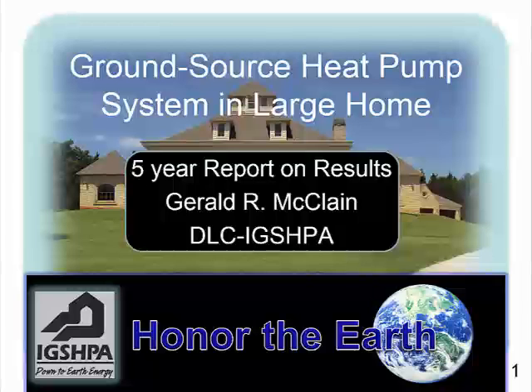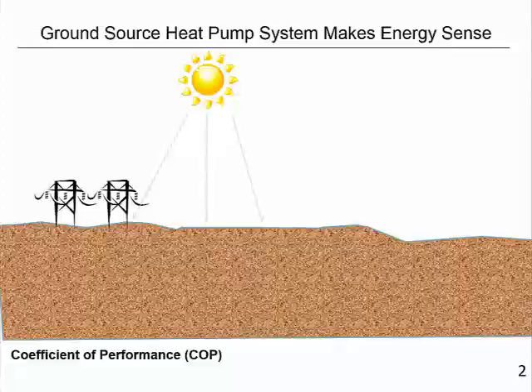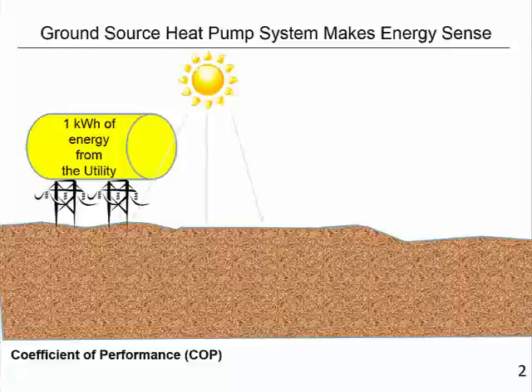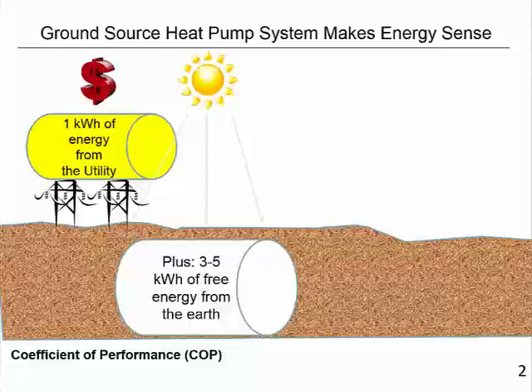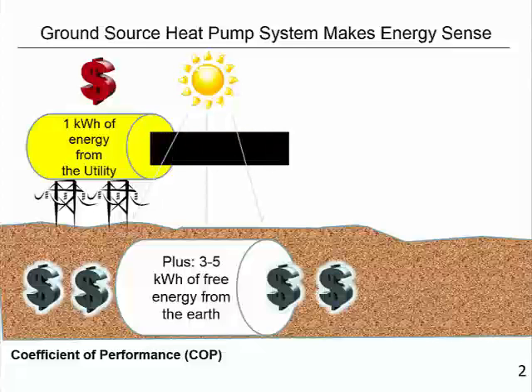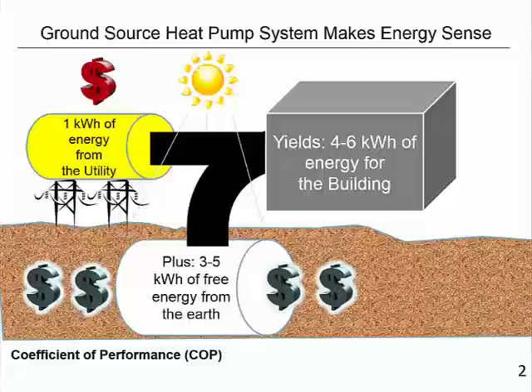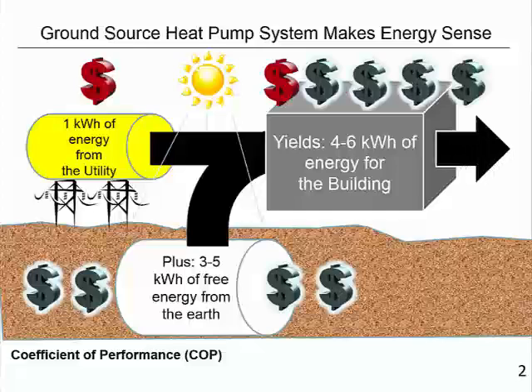I am the Distance Learning Coordinator for the International Ground Source Heat Pump Association, and this is my home. Well, a ground source heat pump system makes energy sense, and this is sort of why. You take 1 kilowatt of energy from the utility, and you take 3 to 5 kilowatts of free energy from the earth, and you put those together, and you'll end up with 4 to 6 kilowatts of energy for the building. That essentially gives you a 400 to 600% efficiency, or a COP of 4 to 6. COP is coefficient of performance.